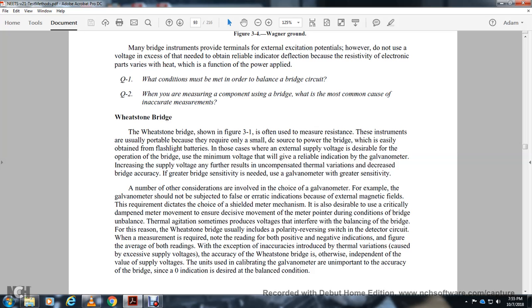The galvanometer should not be subject to false or erratic indications due to external magnetic fields, requiring a shielded meter mechanism. Critical damping of the movement is also desirable to ensure decisive pointer movement. Thermal agitation can produce voltages that interfere with bridge balance. For this reason, the Wheatstone bridge usually includes polarity-reversing switches in the detector circuit, taking both positive and negative readings and averaging them to correct for thermal variation errors.